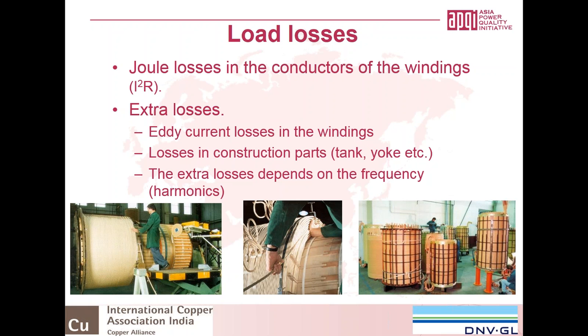If you energize a transformer and also take the current into account, then you will have a magnetic field between the windings, and that electromagnetic field will have some impact on the losses within the windings, within the copper of the windings. Also, you will have some losses in construction parts, as we already saw in the picture before, that there are a lot of construction parts in transformers. For instance, the tank and the yoke. If they are made of iron or another material, they can also have some losses, which are called extra losses. And also, and that's the aim of this presentation, you could have some extra losses which are caused by harmonics.